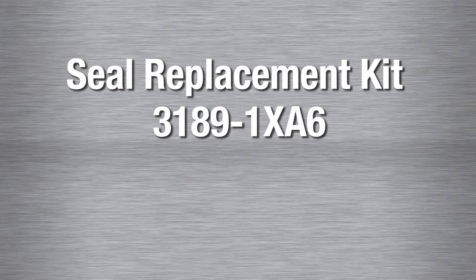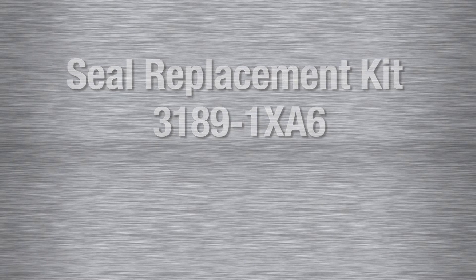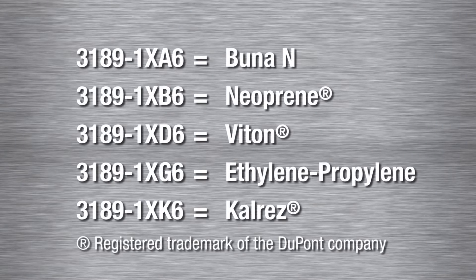All standard Coraflow autogas pumps use the seal replacement kit 3189-1XA6. The letter at the end of the part number after the X indicates the O-ring material. A is the standard configuration and indicates BUNA N. Optional O-ring material is available and indicated with a B for neoprene, D for viton, G for ethylene propylene, and K for Kalrez.